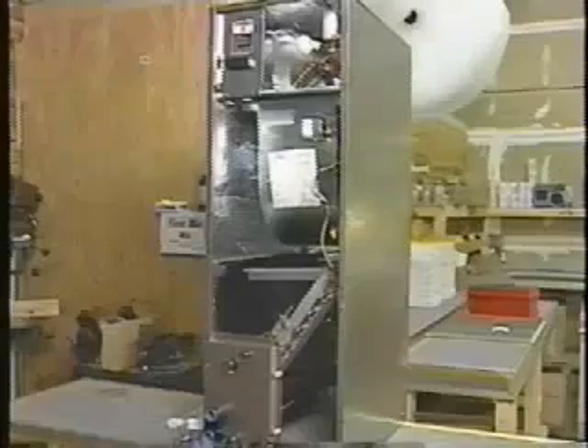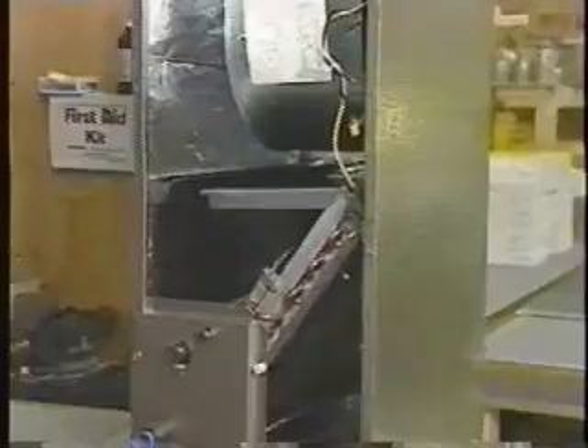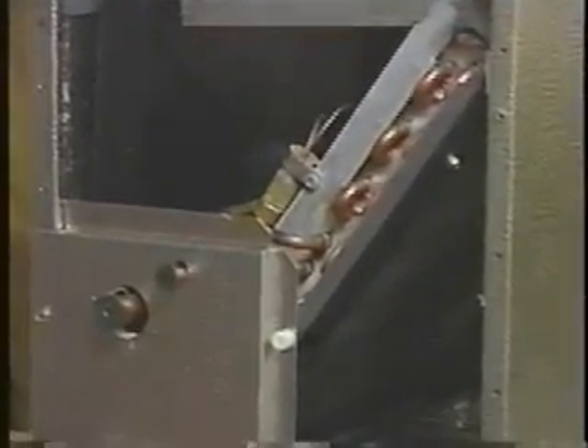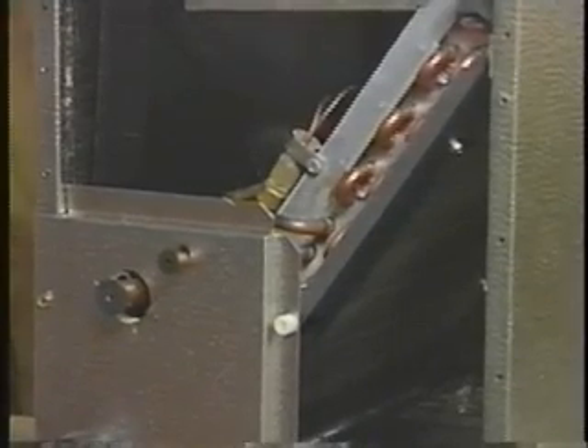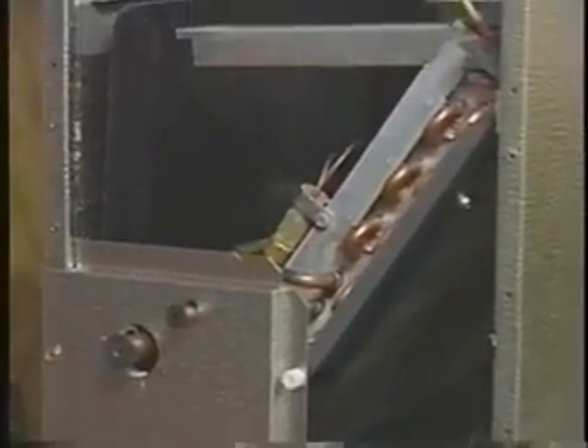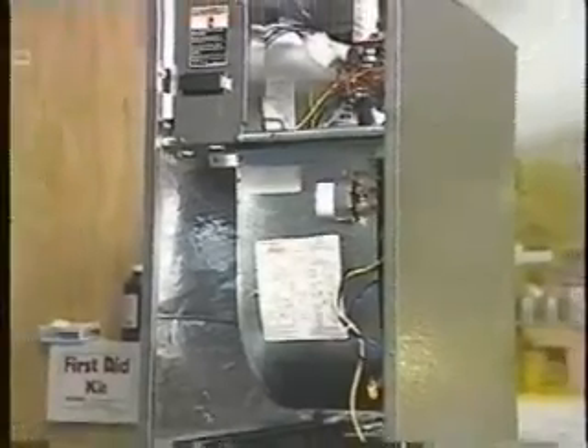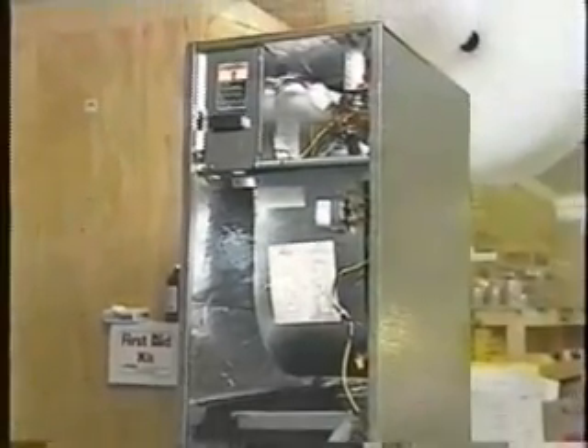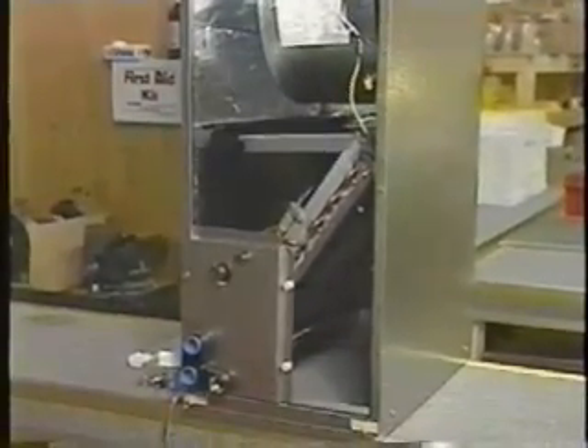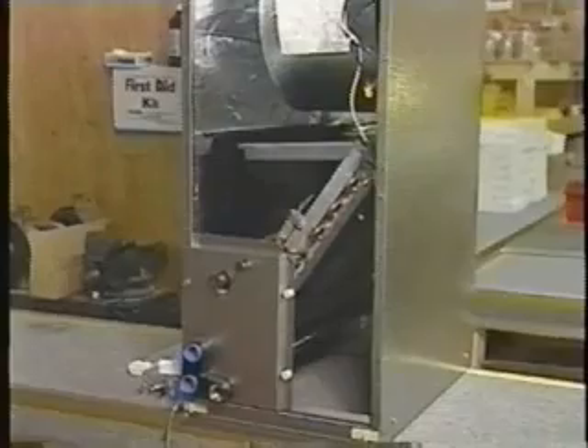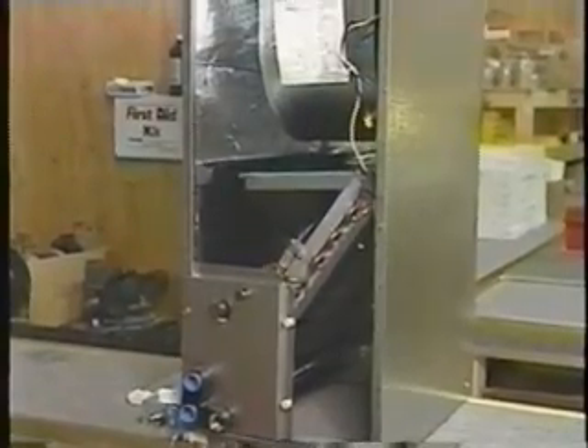There are three basic installation techniques, because there are three different types of coil. This particular installation is a very small carrier slant coil. Normally the fixture would fit in the very back of the fan over top of the coil, but in this case your cabinet is very small, so we'll show you an alternative way to install this, and it should in fact be installed this way anytime you have a slant coil.